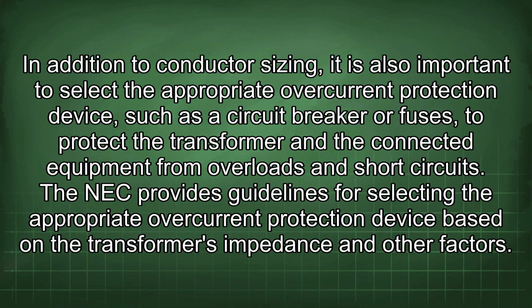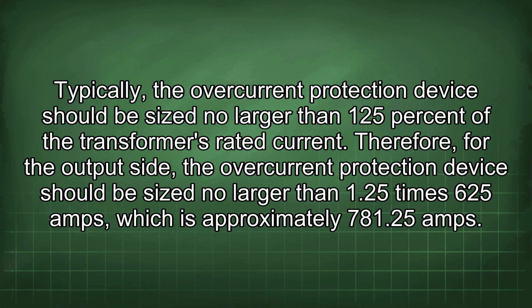In addition to conductor sizing, it is also important to select the appropriate overcurrent protection device, such as a circuit breaker or fuses, to protect the transformer and the connected equipment from overloads and short circuits. The NEC provides guidelines for selecting the appropriate overcurrent protection device based on the transformer's impedance and other factors. Typically, the overcurrent protection device should be sized no larger than 125% of the transformer's rated current. Therefore, for the output side, the overcurrent protection device should be sized no larger than 1.25 times 625 amps, which is approximately 781.25 amps.